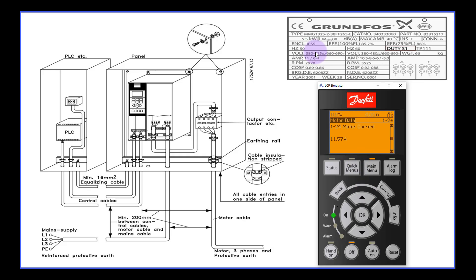This is motor current. The voltage range I selected means the full load ampere will be 11 amperes. If your incoming three-phase AC voltage is between 660 to 690V, your full load ampere would be 6.4A. For my case, my incoming voltage is 415V, so I will key in 11 amperes as my motor current or full load ampere (FLA). I press OK to edit and change it to 11.0, then press OK to accept the value.